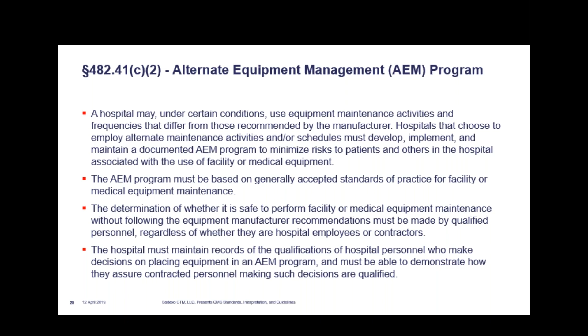They determined an AEM based off of that and say, well, the manufacturer recommends annual, the FDA says annual. Well, we're seeing a lot of failures more frequently than that. By going to a semi-annual PM cycle on certain types of equipment, we see a significant reduction in failures. I mean significant, from maybe 17% down to 2%, just by seeing the system one more time during the year. And we did that based on utilization, as well as what we were experiencing from the repair standpoint or repair for PM. That's a great example of what works.